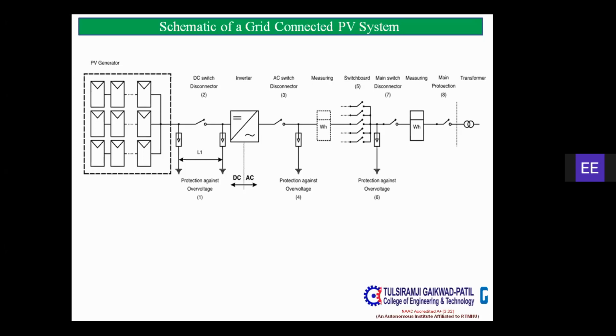Without an inverter, as we have already said, if the loads are DC then it's fine, but mostly we have AC loads available with us. So we have to connect the inverter to our system. Then the AC switch disconnector, then the measuring, of course, we have net metering and gross metering kind of availability as of now. If we have rooftop systems, and if the systems are not rooftop, if it's a multi-megawatt system, then it would be connected directly to the grid with substations like 11 kV or 33 kV, and depending on the output of the system, it could be even more, up to 66 kV as well. So then we have the switchboard of protection devices, and finally, the main protection and the transformer, which would be connected to our substation. So this is the schematic of a grid connected PV system.